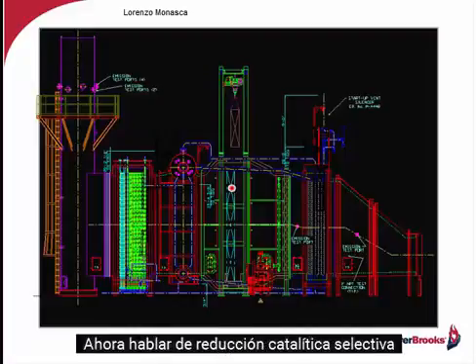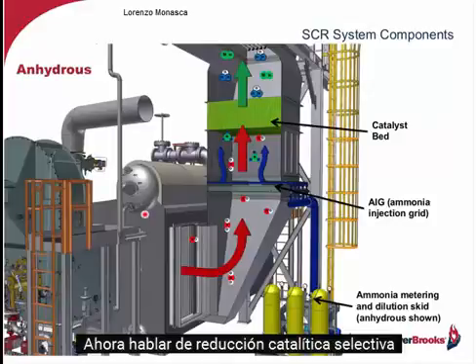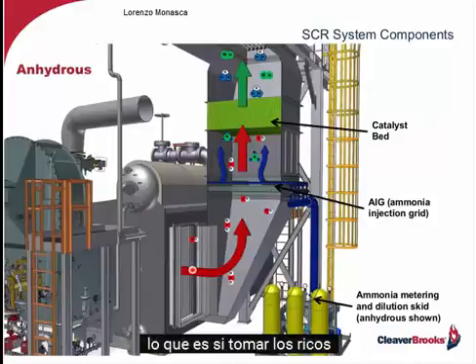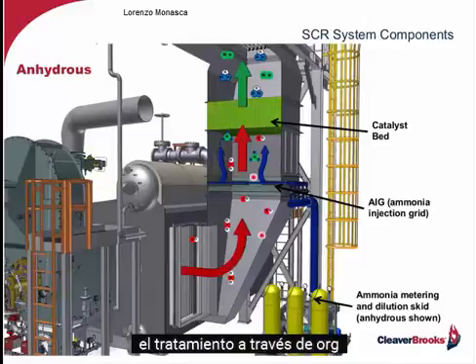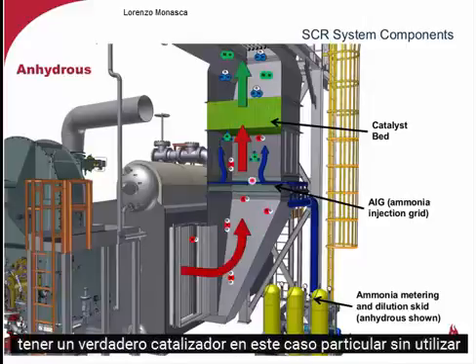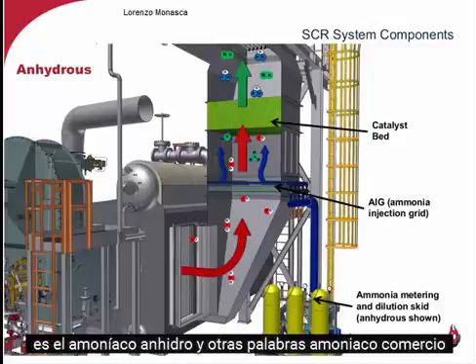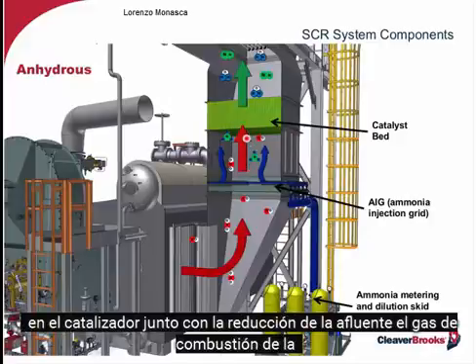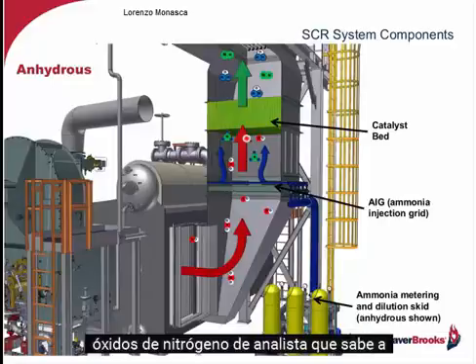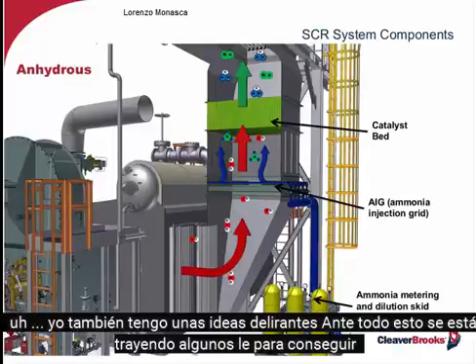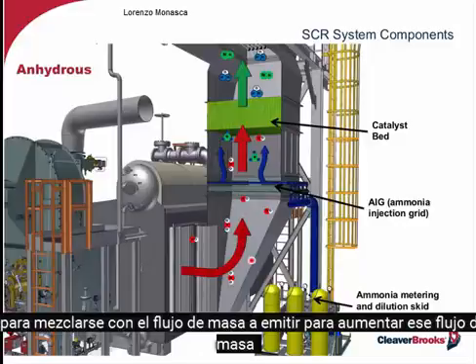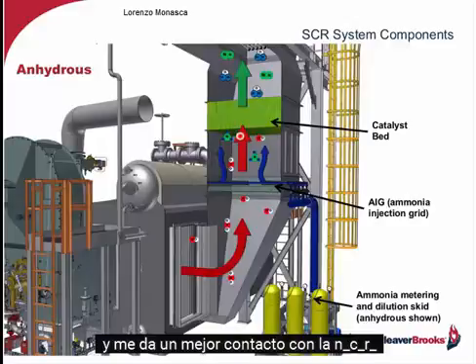Now, speaking of selective catalytic reduction, what that is, it's taking the effluent and passing it through a catalyst. In this particular case, what I'm using is anhydrous ammonia, in other words, straight ammonia, which is being injected into the catalyst along with the flue gas effluent, reducing the nitrogen oxides, NO and NO2. I also have a dilution skid, and all this is bringing in some ambient air to mix with the mass flow of the gas to increase that mass flow and give me better contact with the SCR.